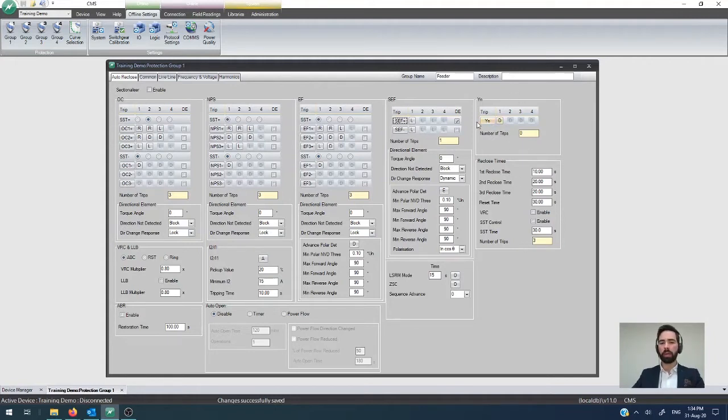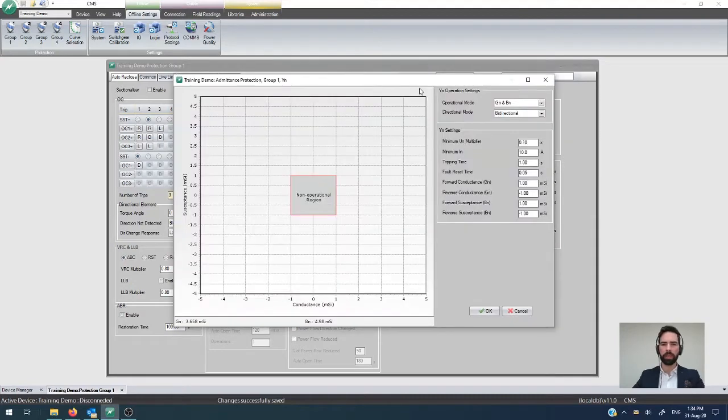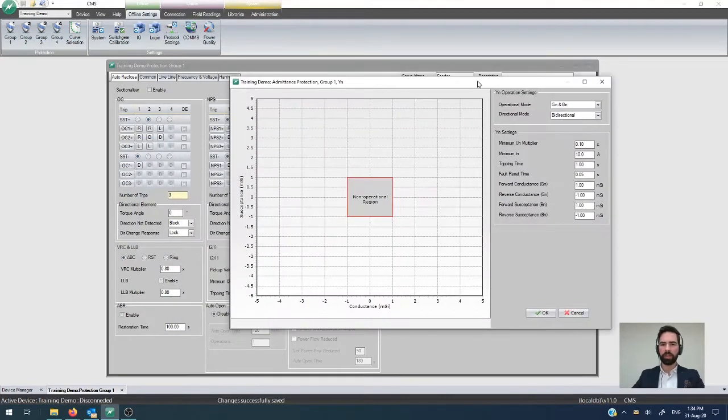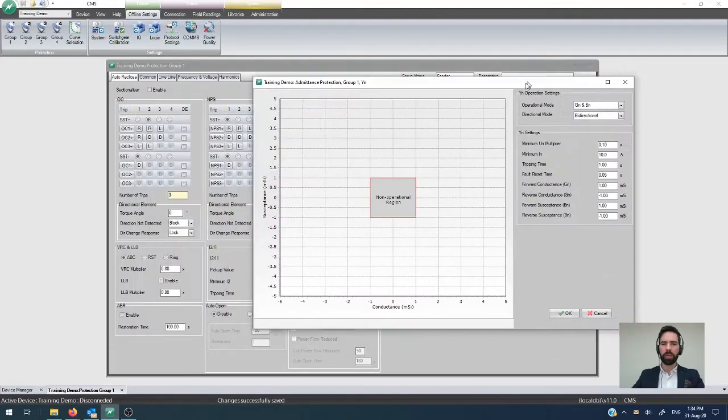So it has a slightly different configuration map to what the other elements do in that neutral admittance rather works in values for conductance and susceptance instead of current components.